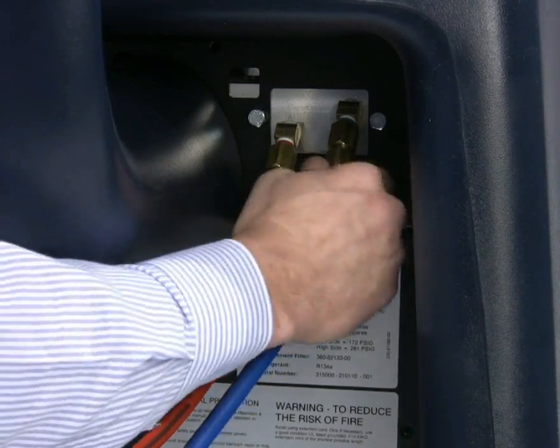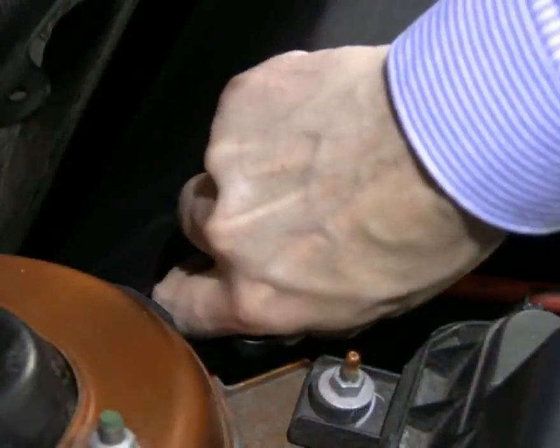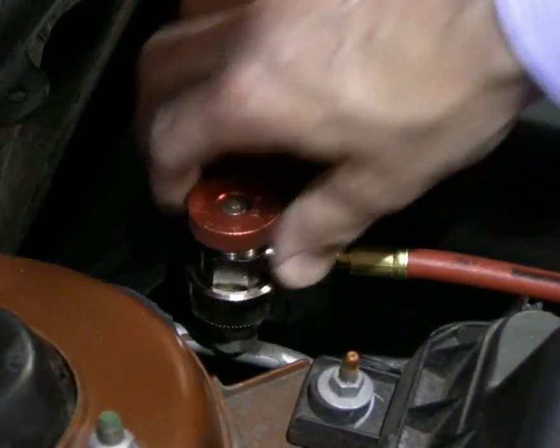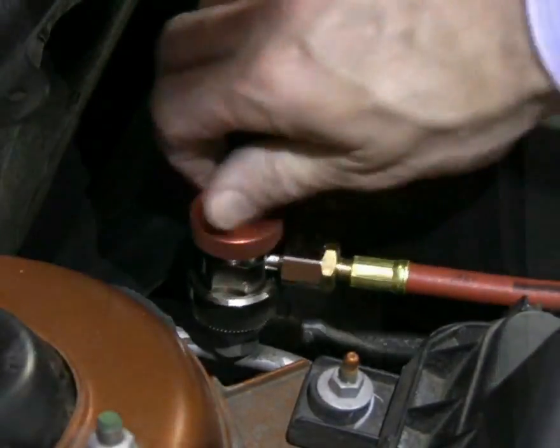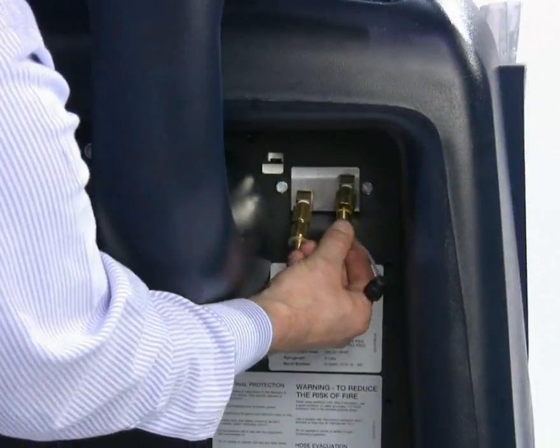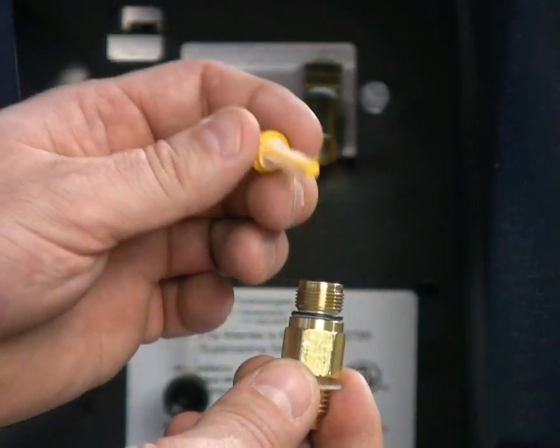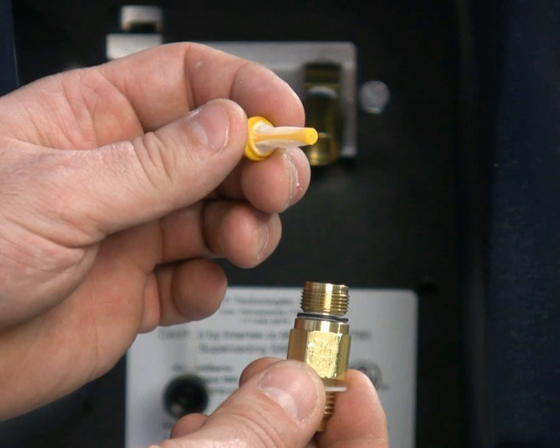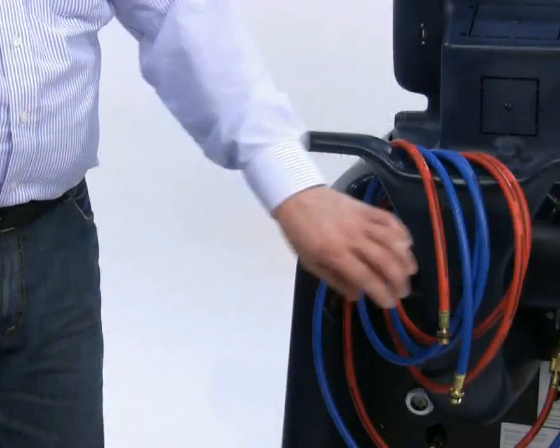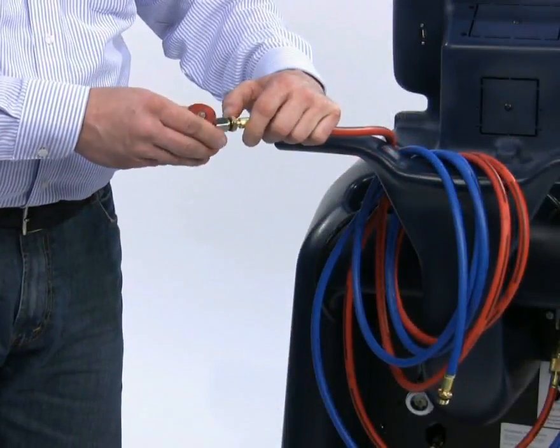When you replace the service hoses, do not use mechanical tools like pliers to tighten the hoses. Finger tight is all it takes. Also, if you experience inability to draw a vacuum with the RHS980, check your hose connections for proper sealing. As illustrated previously in the video, the hose screens inserted between the service hose ends and the inlet-outlet ports of the RHS980 serve as the first line of protection to keep contamination out of the internal fluid passages of your machine. The hose screens should be replaced when the vacuum pump oil is replaced, and especially if you experience abnormally slow service times. Service couplers are not normally thought of as service or consumable items.